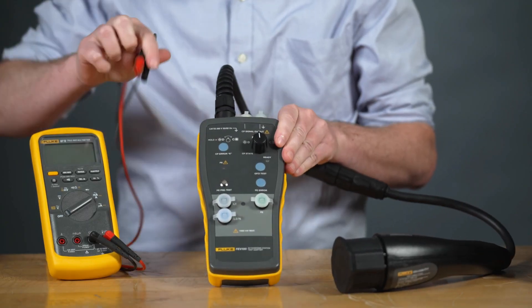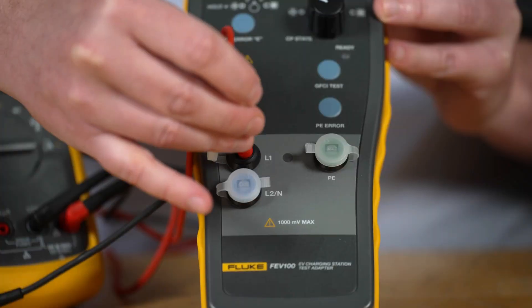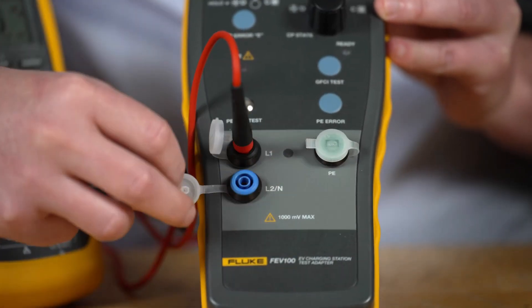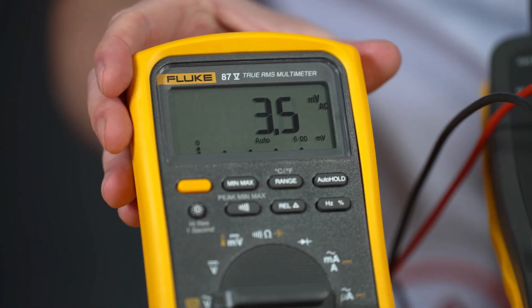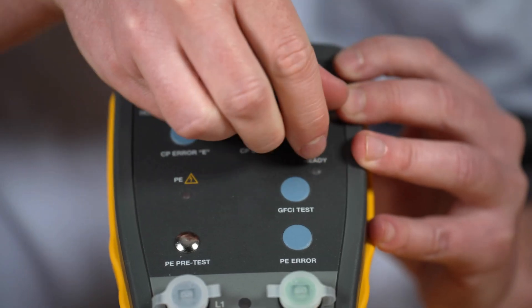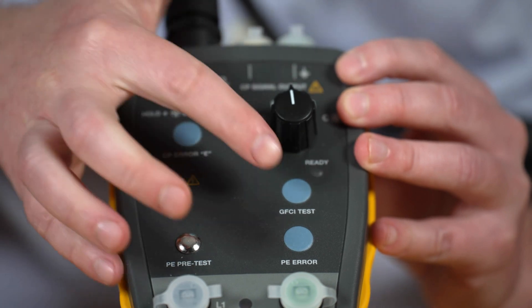Then, connect the multimeter — it's recommended to use a Fluke 87 V. Check the output voltage and measure the continuity of the PE connector. You can also test GFCI trip time and leak current.